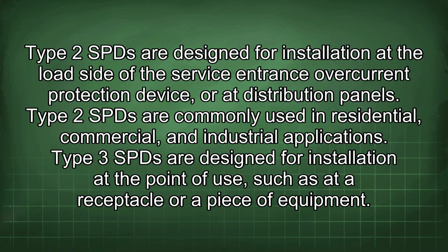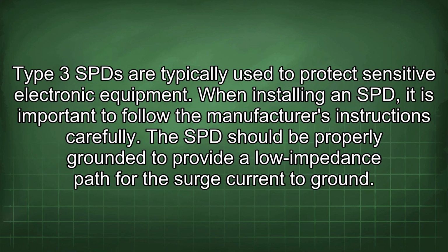Type 2 SPD are designed for installation at the load side of the service entrance overcurrent protection device or at distribution panels. Type 2 SPD are commonly used in residential, commercial, and industrial applications. Type 3 SPD are designed for installation at the point of use, such as at a receptacle or a piece of equipment. Type 3 SPD are typically used to protect sensitive electronic equipment.